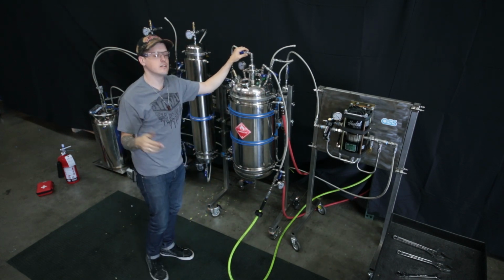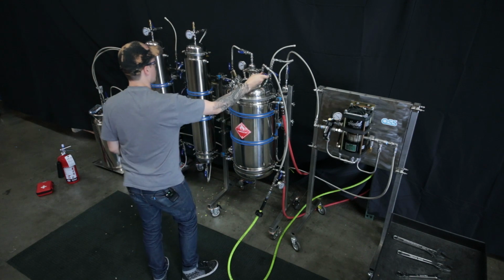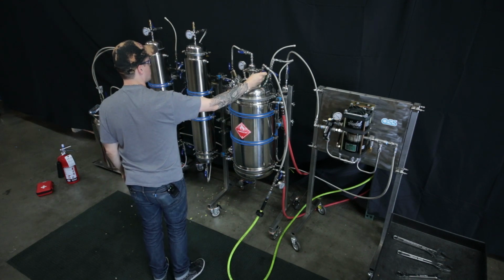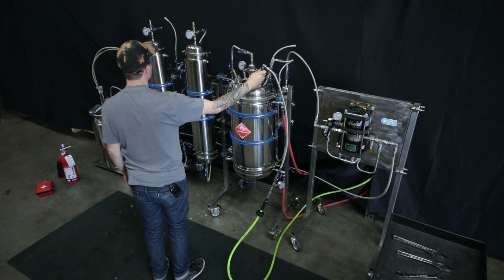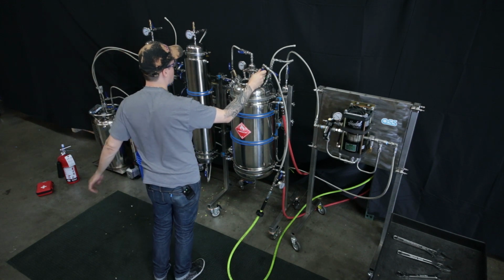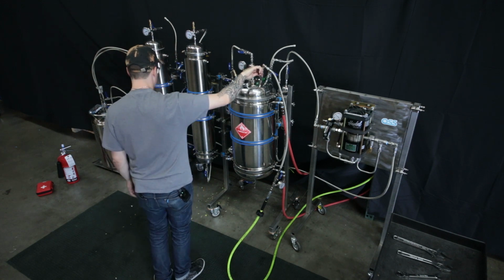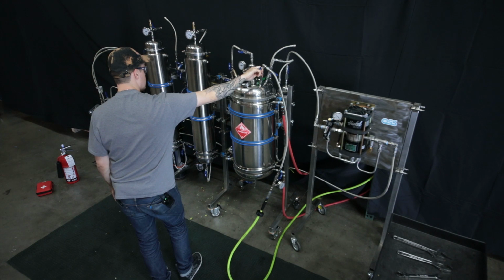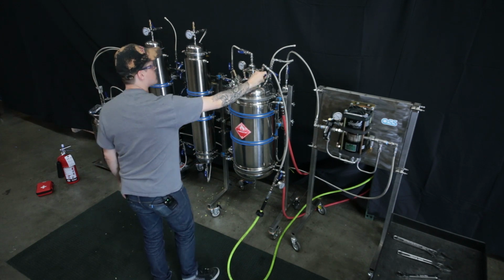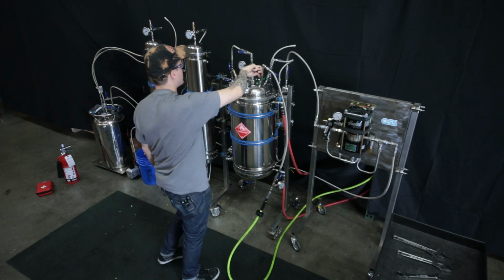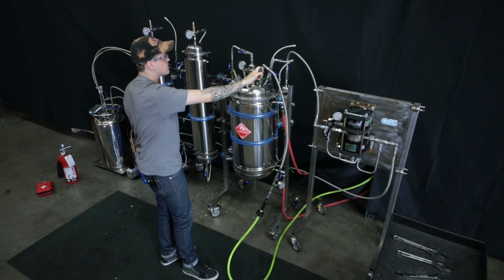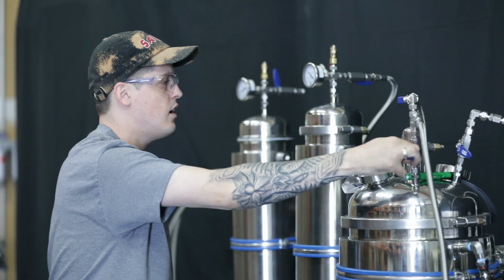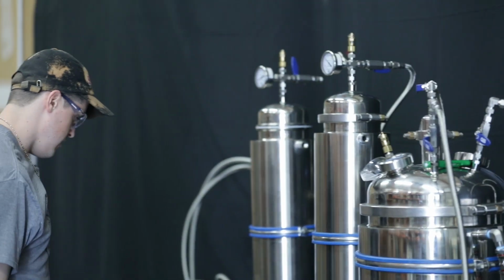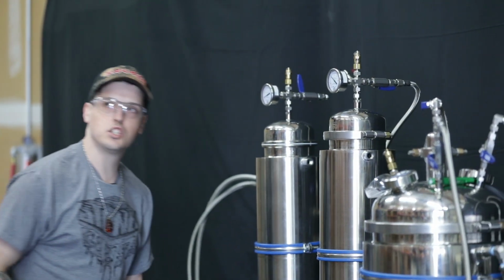Now I'm adding air into the system. I'm going to pressure check this column as well as the evaporation vessel. I'm going to start slow in stages. So right now I'm just going to go to like 30 pounds per square inch, 30 psi, and we're going to turn off our valve. We don't want to go shooting up in pressure before we find any leaks.